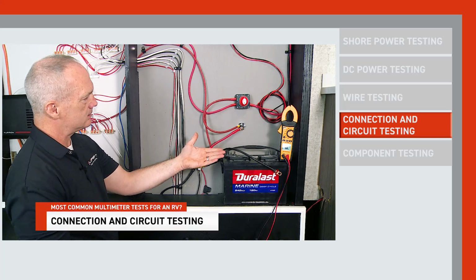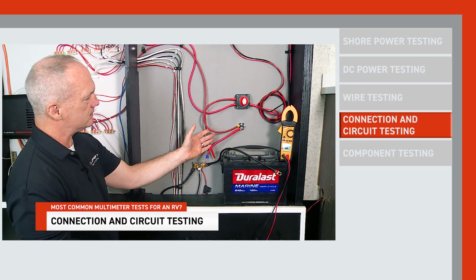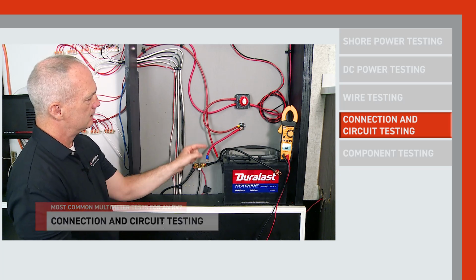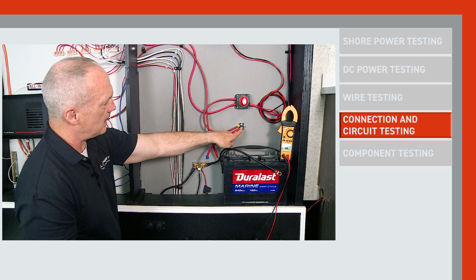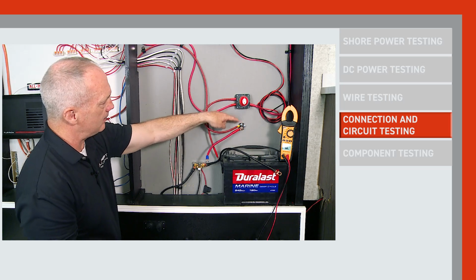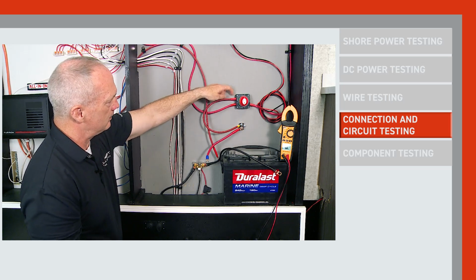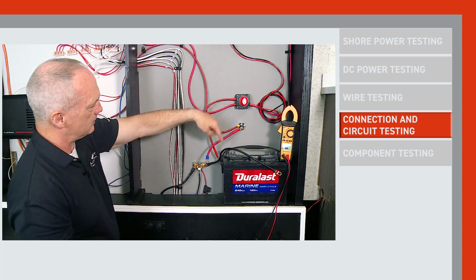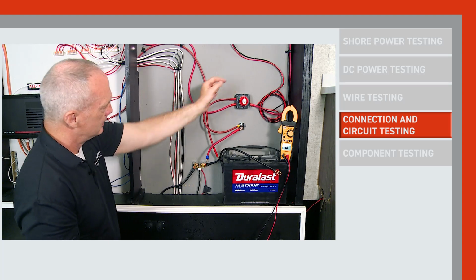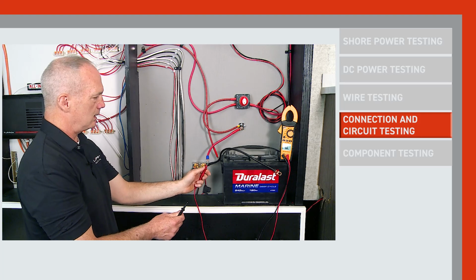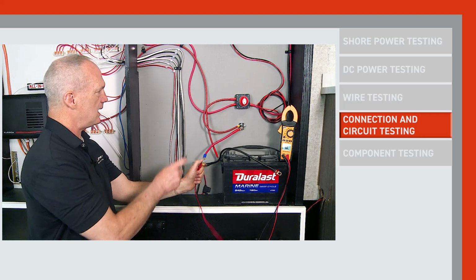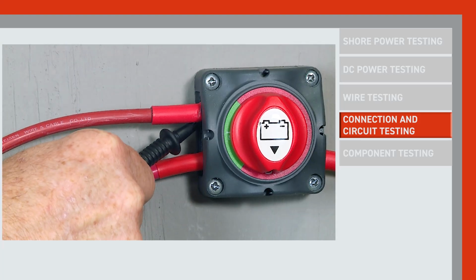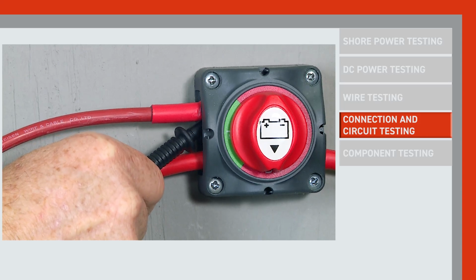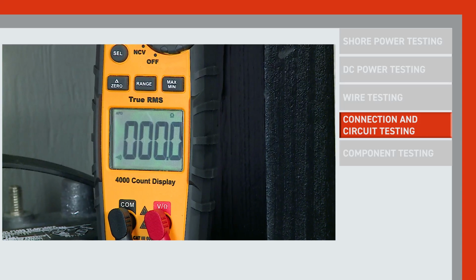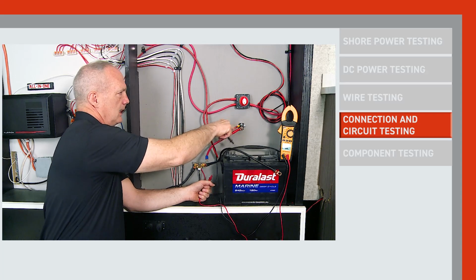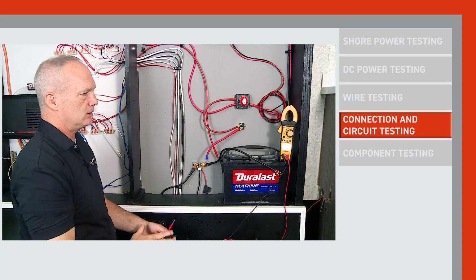The next test checks the components in a circuit. So I'm not only checking this wire, but the mini breaker all the way up to the quick disconnect. I put one lead on one side and one on the other, checking connectivity through the mini breaker and the wiring included in that circuit.